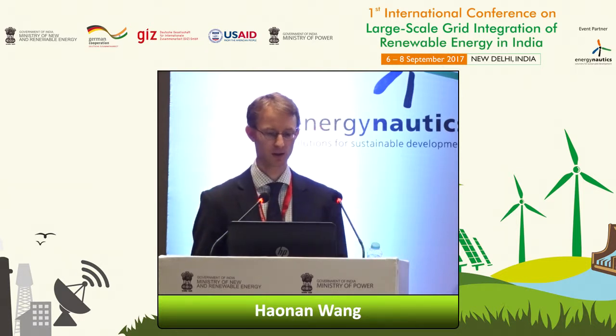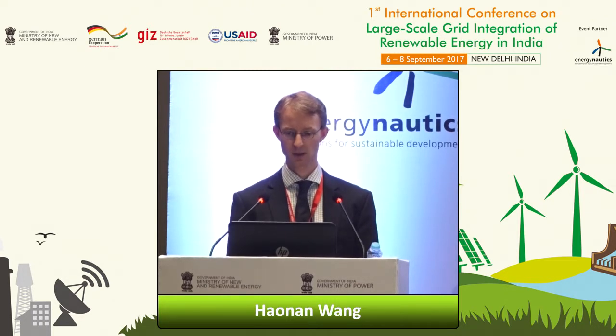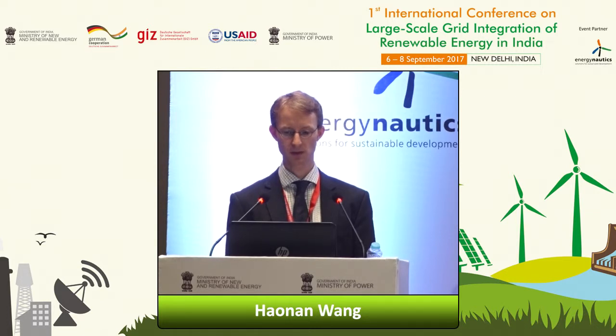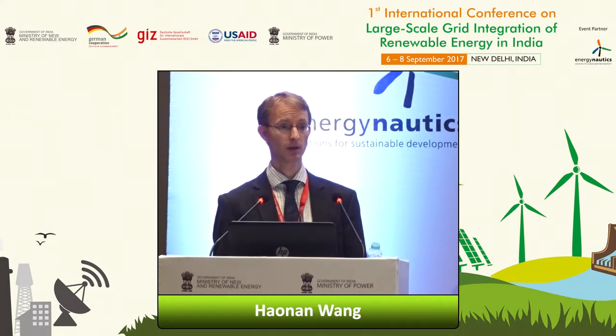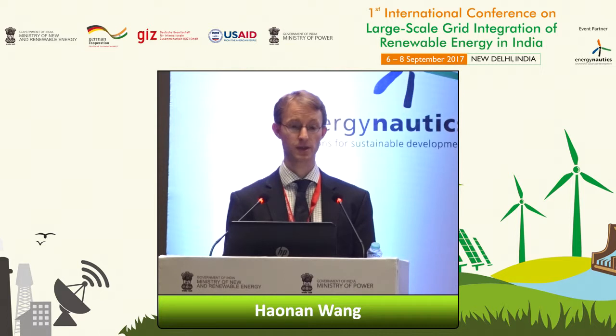So just giving here some impressions. We did that for this case study as well. We developed the controller in this external PC, where the central management is implemented. And then we had a real-time simulation with an Opal-RT real-time simulator of the real medium-low voltage grid there, implementing the models for the power plants and integrating also this local reactive power from voltage characteristic. We applied that, and the result was that it's operating stable and does what it should.